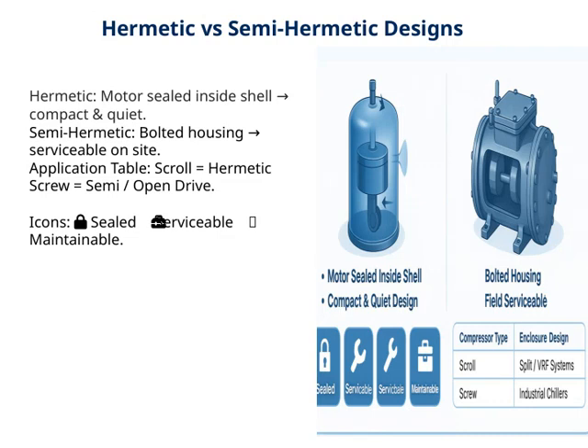Let's take a closer look at hermetic versus semi-hermetic designs. Hermetic systems have the motor completely sealed inside a shell, which makes them very compact and also quite quiet. This sealing helps protect the motor from external contaminants and reduces noise levels. On the other hand, semi-hermetic designs feature a bolted housing, which means they can be opened and serviced on site. This makes them more accessible for maintenance and repairs when needed.